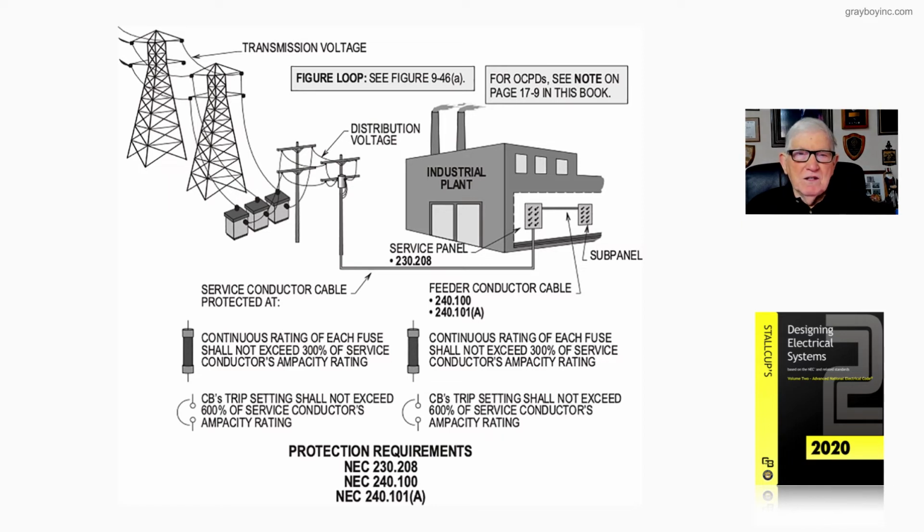240.101A in the NEC. Now for protection of these transformers you see in the illustration, just go to table 450.3A and you can pick up the same percentages that you see here for these conductors. And you know those percentages, they raise those percentages up like that usually when they have in the facility equipment requiring inrush current to start and operate and drive a particular load.